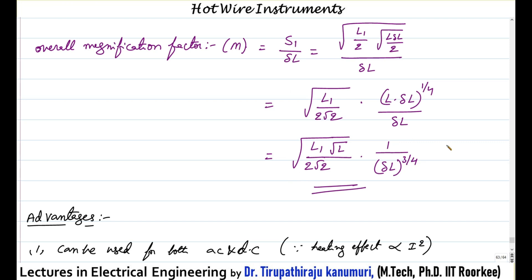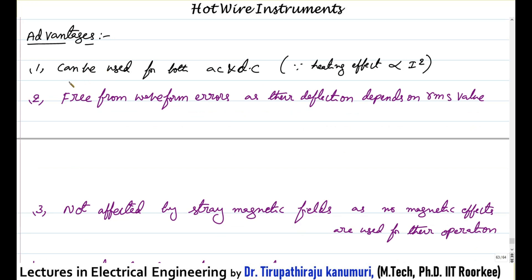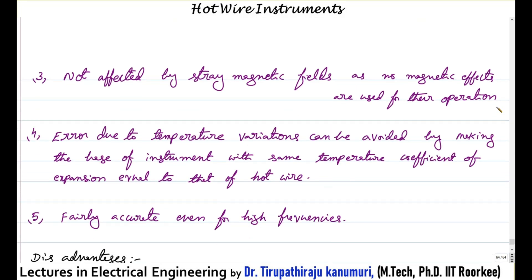Because of this entire arrangement, the small delta L is magnified so many times that we get a huge displacement in the pointer, allowing measurement of even the smallest change in current. Advantages: it can be used for both AC and DC since heating effect is proportional to current square; it is free from waveform errors as deflection depends on RMS value only; and it is not affected by stray magnetic fields because there is no magnetic effect in the operation of this instrument.